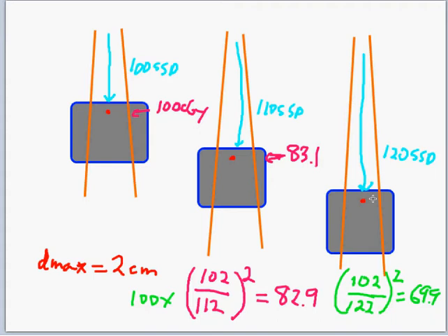And let's say I put my ion chamber there and I set it up the same, and I measured, I don't know, let's say it was 70.1 or something. So again, it's close, and we would say yes, inverse square seems to be working. It's something we can use in our calculations. We don't have to go measure those spots. We can just do inverse square, and it works for photons.